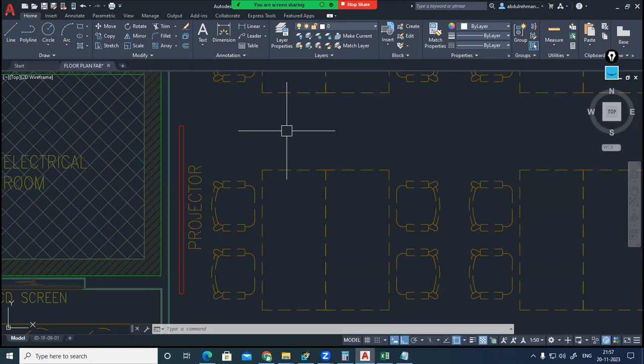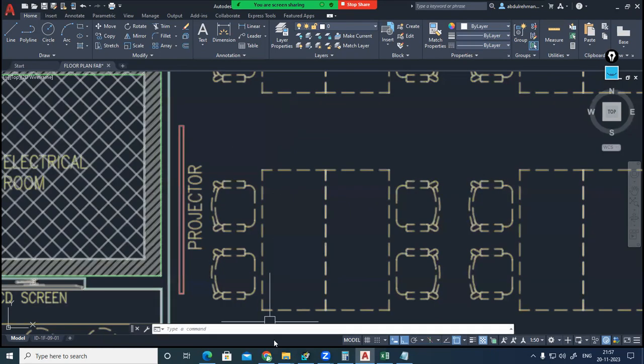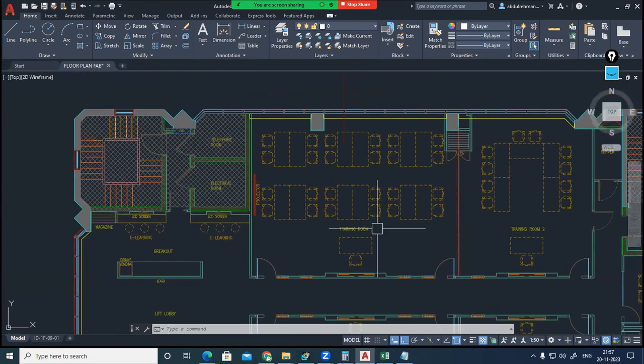Training room one, it will come. So for the rated load of the projector, since it is a light fitting, you should consider the entire load as radiation. Okay. Rated load, how can we find it? From the manufacturer only. Any manufacturer catalog you can refer to. Anyway, for the conventional LED projectors we use inside training room one and all, it will be a maximum of 300 to 500, less than 500 watts only.